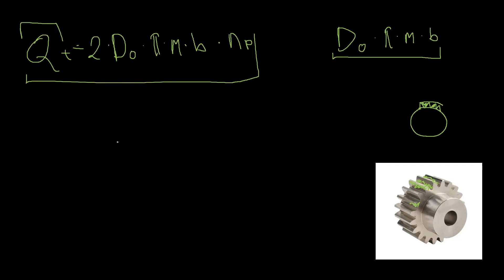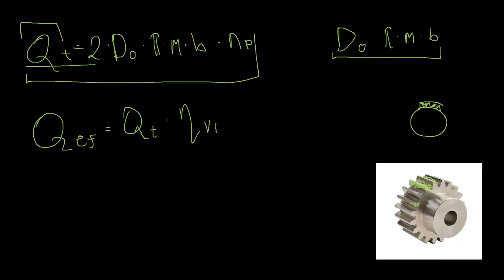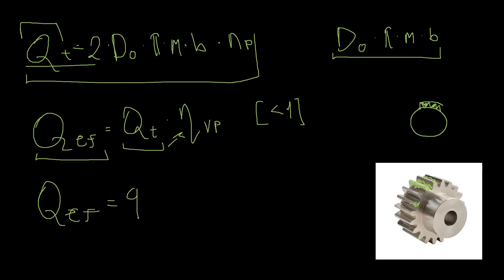Because of losses and clearances in the pump, when we calculate the effective flow — as opposed to theoretical flow without efficiency factors — q_effective equals the theoretical flow times the volumetric efficiency of the pump. We must multiply by efficiency, which is always less than one, so effective flow is smaller than theoretical flow because some flow is lost in the pump clearances. The effective flow is: q_eff = qp times n times the volumetric efficiency.